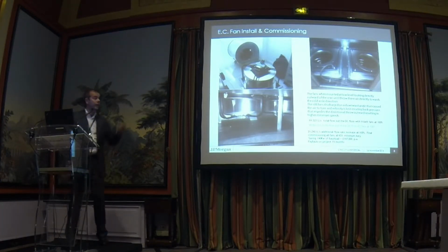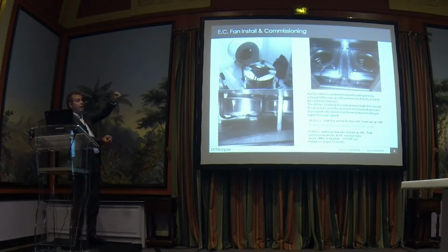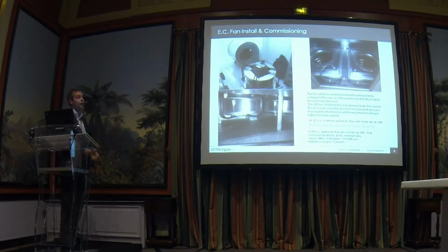You could stand in the data hall down the back end. I held the anemometer in the air and I can get 500 litres of air a second just going through the main corridor just by holding it up. And you could stand there and your jacket would start to flap. That's just in the vacuum going back through these machines.